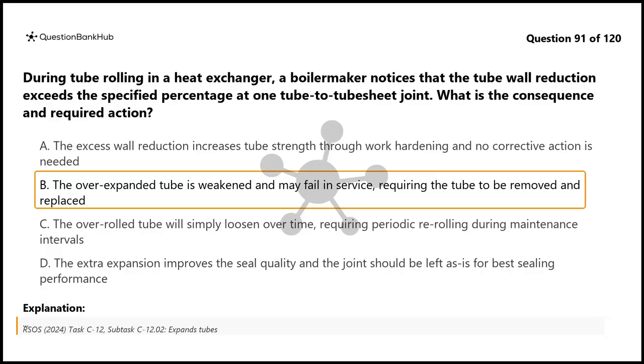The correct action is to remove the defective tube by drilling or collapsing it out of the tube sheet and installing a replacement tube. Overrolling does not improve strength through work hardening beyond a certain point; instead, it causes embrittlement. The joint does not simply loosen over time, and the excess expansion does not improve seal quality.